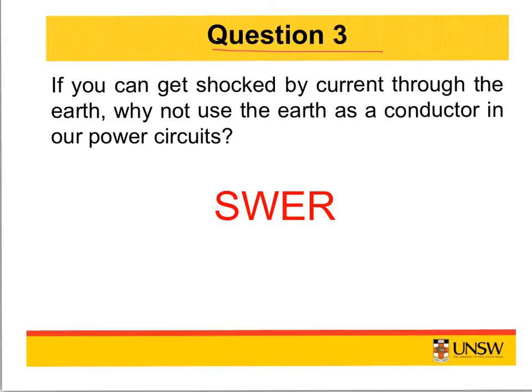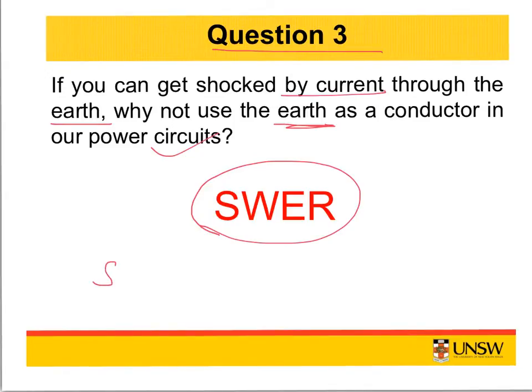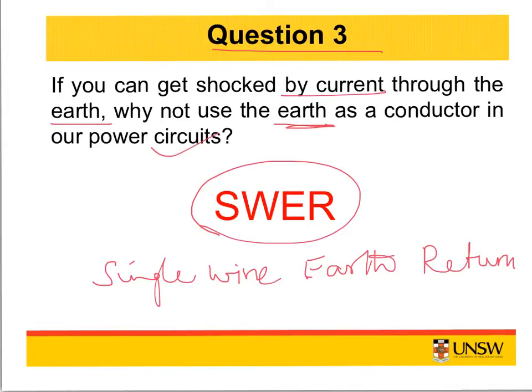Now you come back to another question, question 3. So if you get shocked by current through the earth, why not use the earth as a conductor in our power system? So we have an answer to that, which is called the SWER system. SWER is a single wire transmission line, which is called single wire earth return. So this is a single wire transmission line for supplying single phase electrical power from an electrical grid to remote areas at low cost. The SWER line is a single conductor that may stretch for tens or even hundreds of kilometers, so 10 to hundreds of kilometers, with a number of distribution transformers along its length.